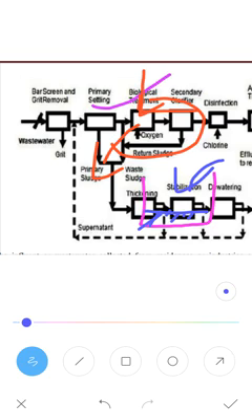The effluent which comes out of the secondary clarifier is fed into the disinfection tank, where chlorine is added to the wastewater to kill the germs and pathogenic bacteria present in the water. Then the water which comes out from the disinfection tank, with germs removed, goes through the final and advanced tertiary treatment process, after which the water can be directly discharged to nearby water courses.